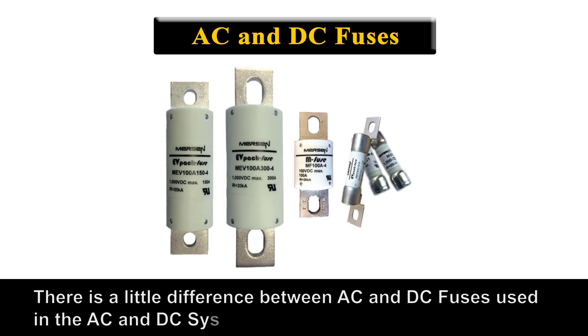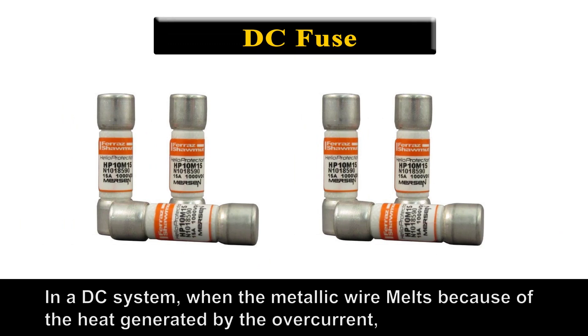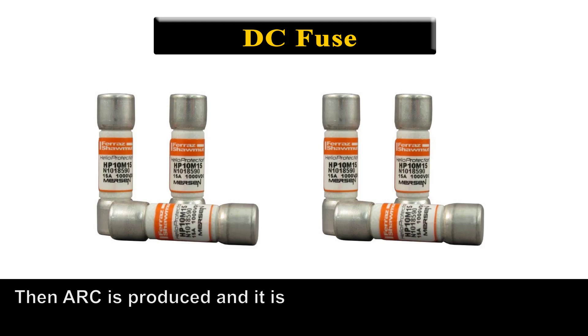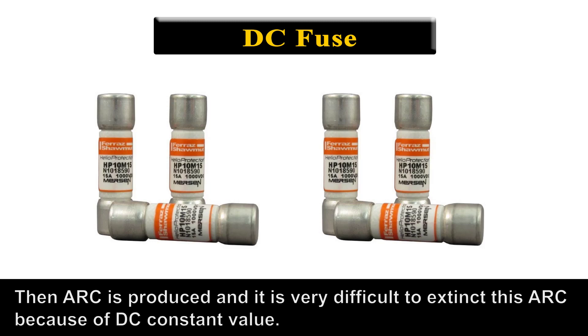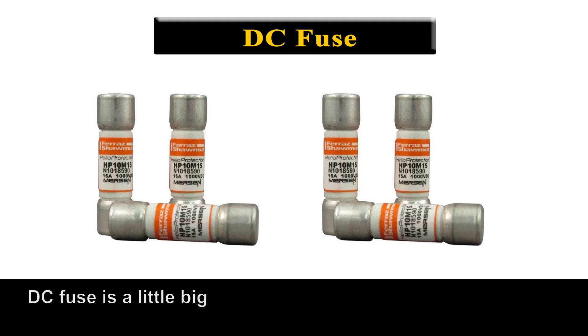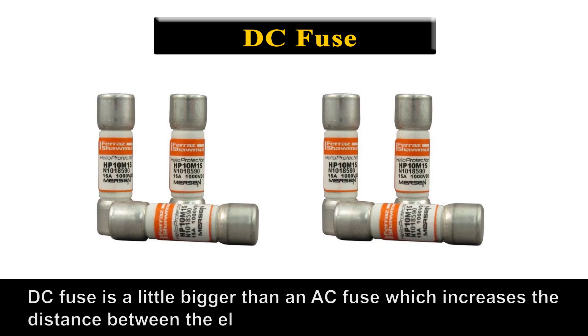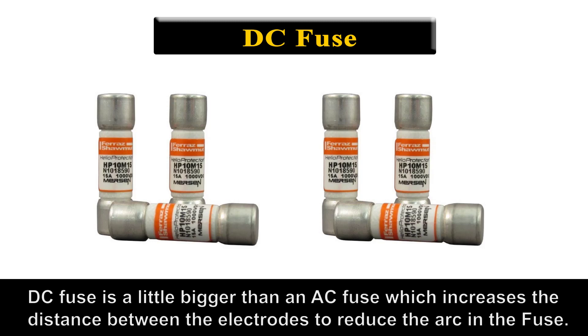There is a little difference between AC and DC fuses used in AC and DC systems. In a DC system, when the metallic element melts because of the heat generated by the overcurrent, an arc is produced and it is very difficult to extinguish this arc because of the DC constant value. So, in order to minimize fuse arcing, DC fuses are a little bigger than AC fuses, which increases the distance between the electrodes to reduce the arc.